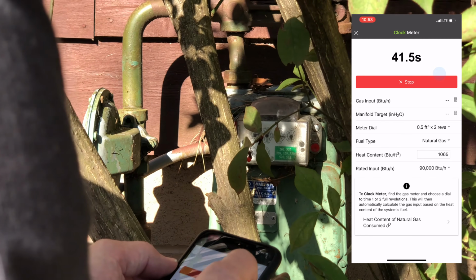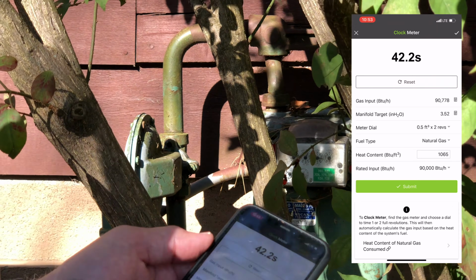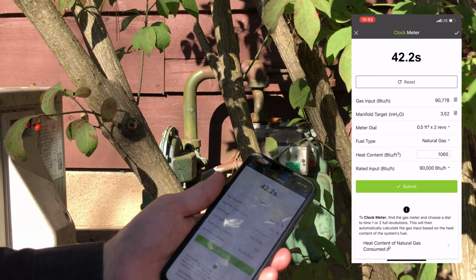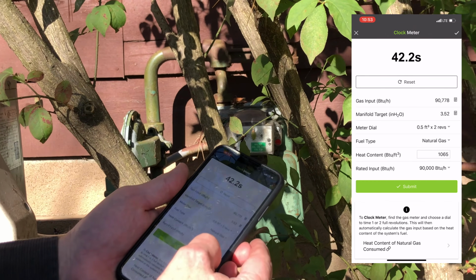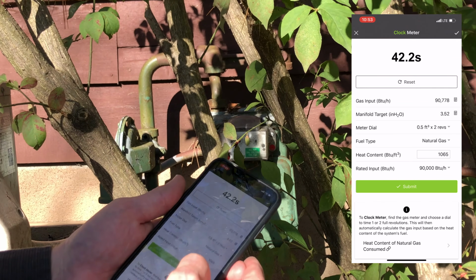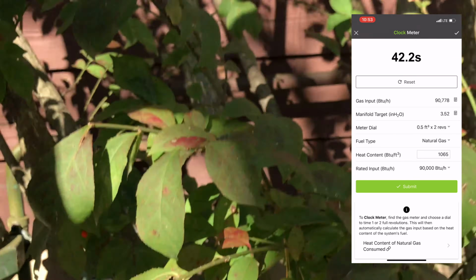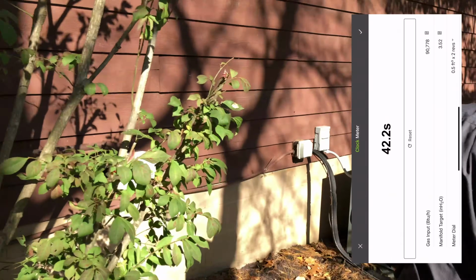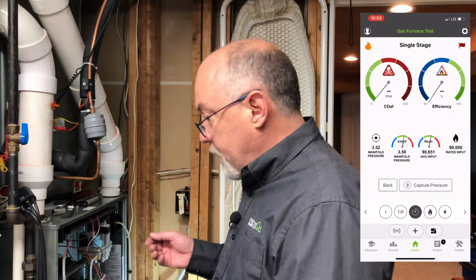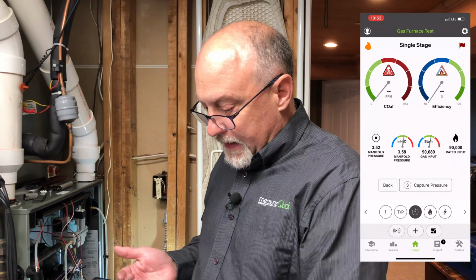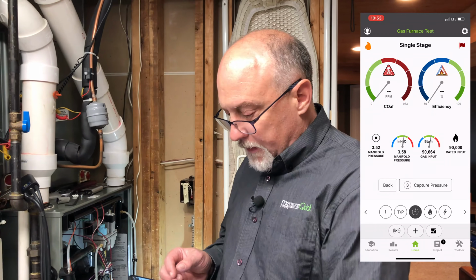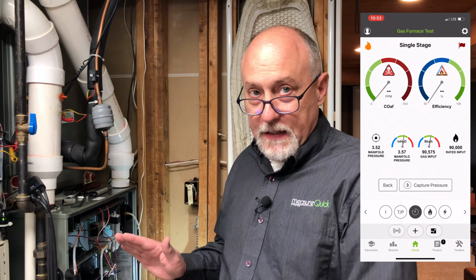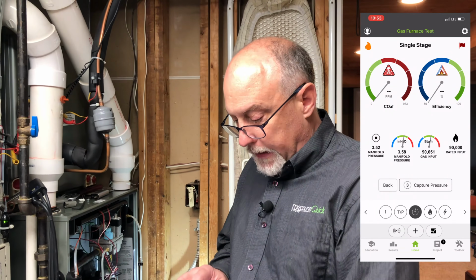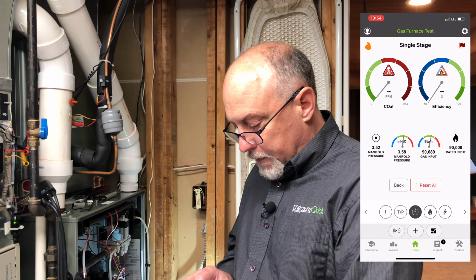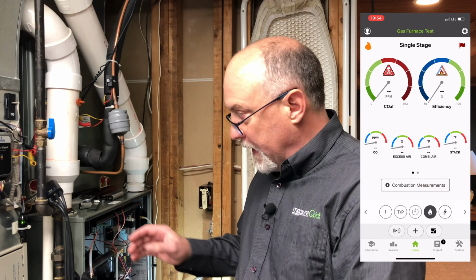Well, stop. And so now I've got my input here at 90,778. So my target manifold pressure is 3.52 inches. So we'll go ahead and we'll go in the office here in the shop. So the target manifold pressure looks good. We're at 90,689. I'm not even going to mess with it because 90,000 is the input. It's pretty much right on the money. So I'm going to go ahead and hit capture pressure here. And then I'm going to go through and take a look at my combustion readings.